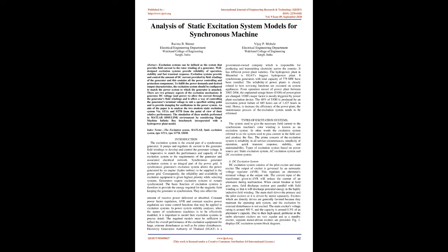3. Excitation voltage reaches a peak of +4.8 pu from the initial value of -2.0 pu up to 0.8 sec and oscillates for 4.0 sec and reaches steady state value after 5 seconds. 4. The load angle of generator rises from -28 to 58 during 0.7 sec and then oscillates for 3.0 sec and attains steady state after 5 seconds.